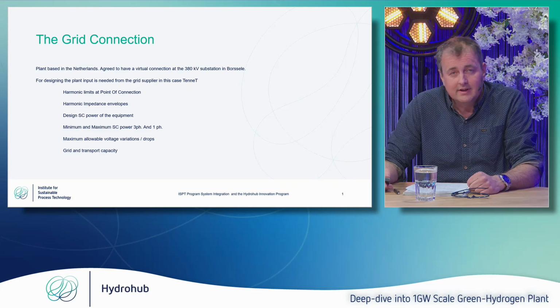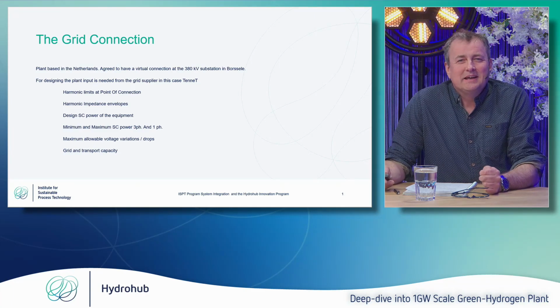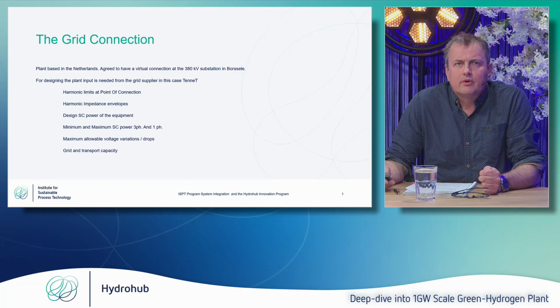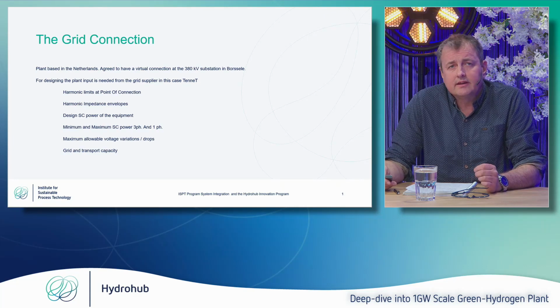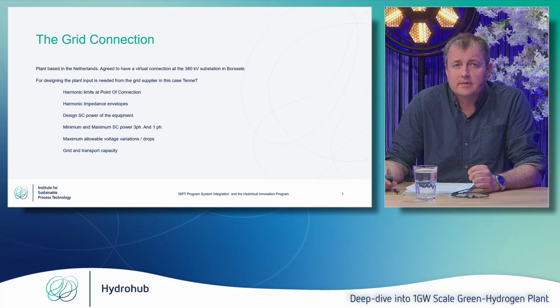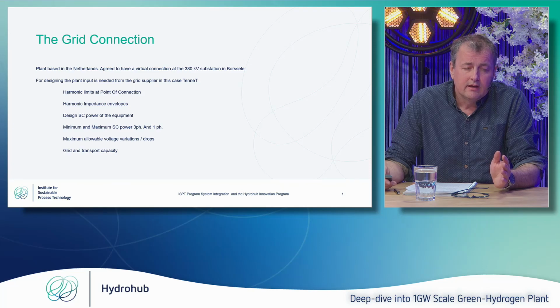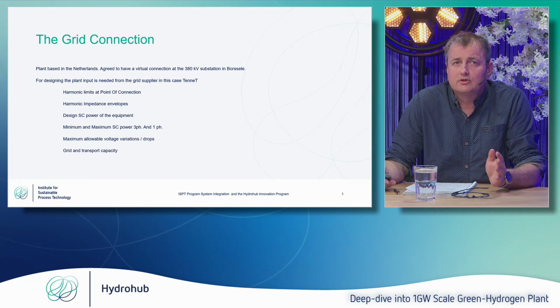The numbers, they go everywhere nowadays. So it's 1 gigawatt. And for each and every operation point, we needed to stay within those limits. And that was quite difficult to achieve. I will come back to the harmonic limits in the next sheet. Another thing is, if you want to do design and stay within the limits, you need your harmonic impedance envelope. So basically, to be compliant, you need to have the impedance for each and every harmonic. So that is also what you need to ask the grid supplier.